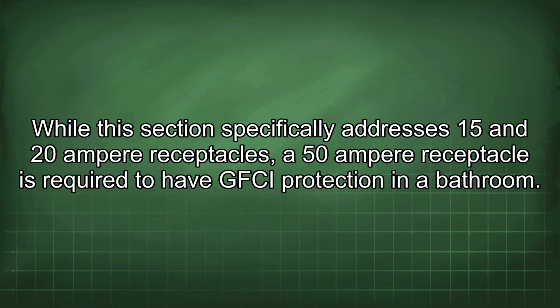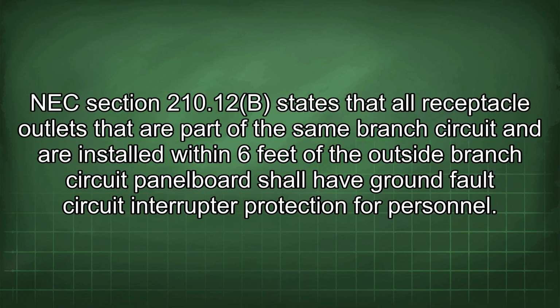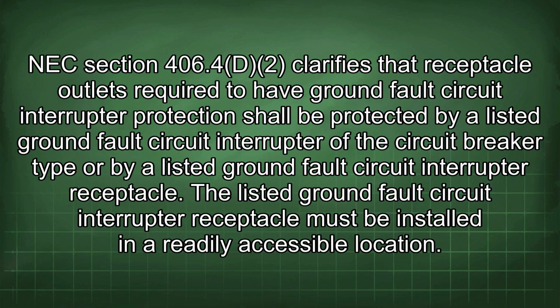in a bathroom. NEC Section 210.12b states that all receptacle outlets that are part of the same branch circuit and are installed within 6 feet of the outside branch circuit panel board shall have ground fault circuit interrupter protection for personnel. NEC Section 406.4d2 clarifies the receptacle outlets required to have ground fault circuit interrupter protection shall be protected by a listed ground fault circuit interrupter of the circuit breaker type or by a listed ground fault circuit interrupter receptacle. The listed ground fault circuit interrupter receptacle must be installed in a readily accessible location.